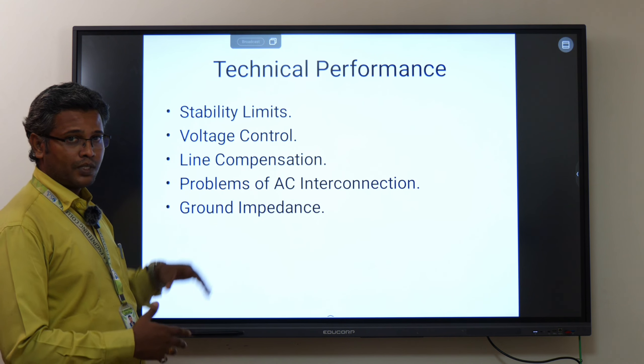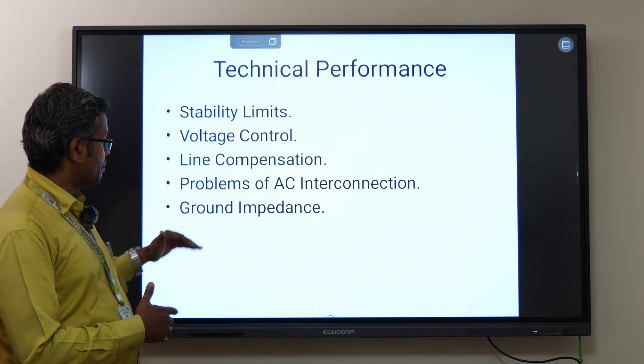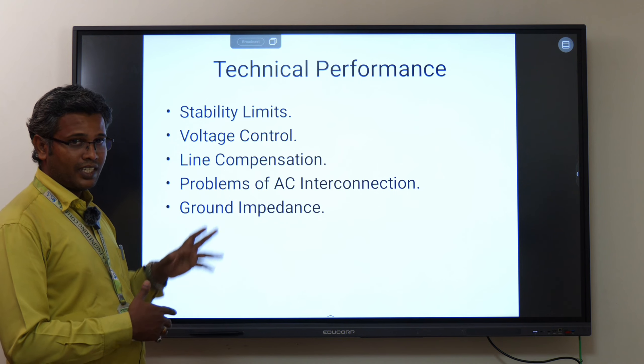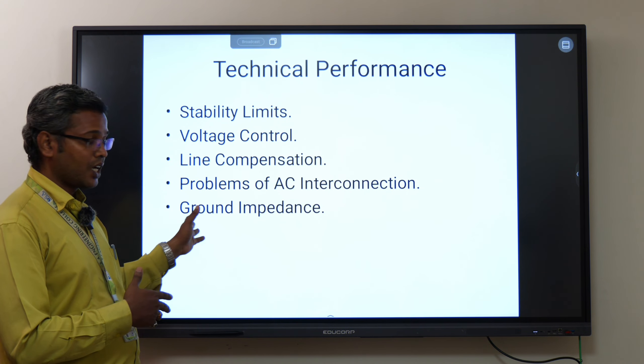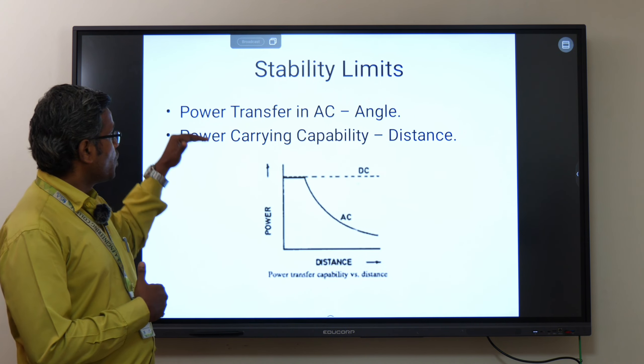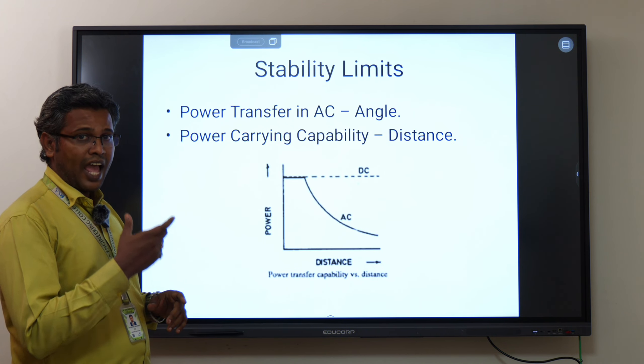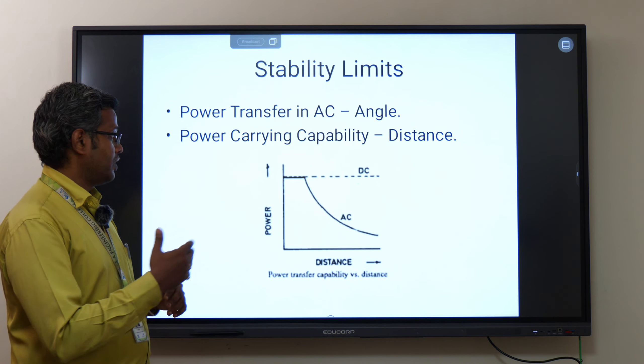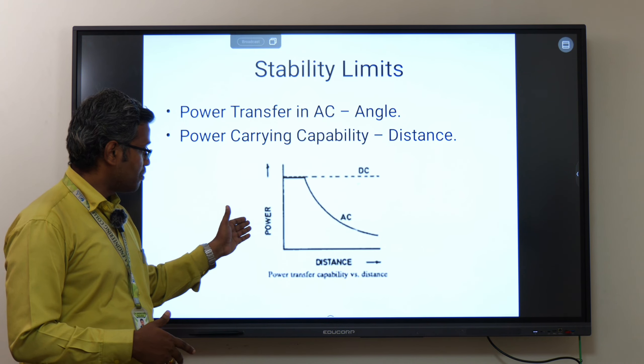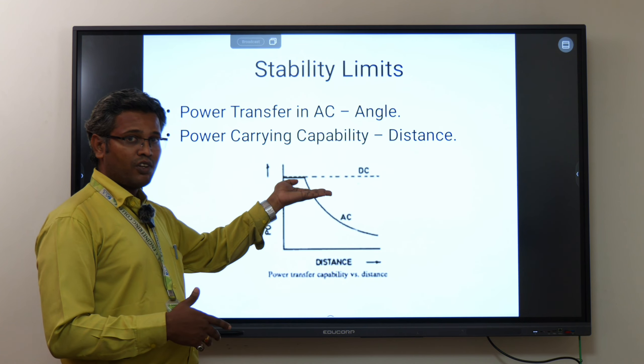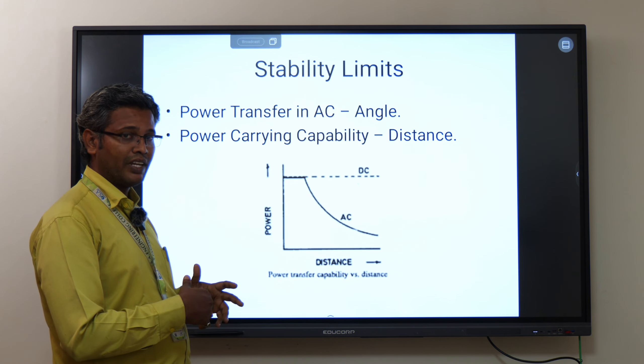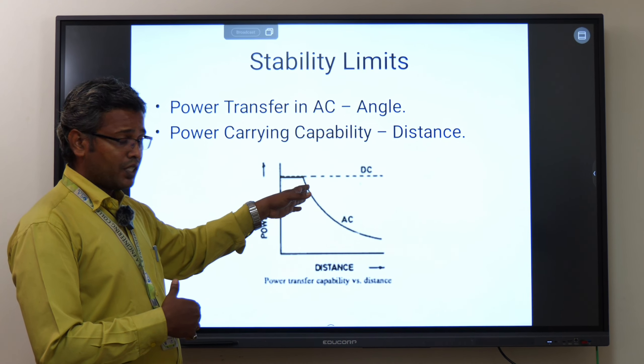Next, with respect to technical performance, we consider five parameters: stability limits, voltage control, line compensation, problems of AC interconnections, and ground impedance. For stability limits, power transfer in AC depends upon the voltage angle between the two ends. For DC, the power transfer capability is constant — it does not vary with distance — which is why for long transmission we prefer DC.